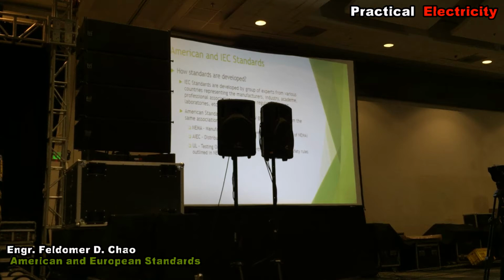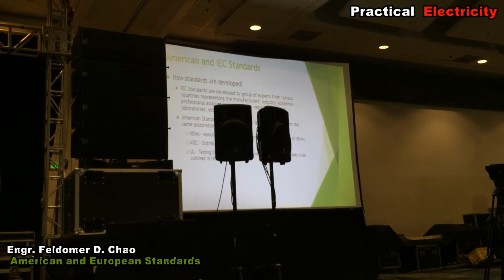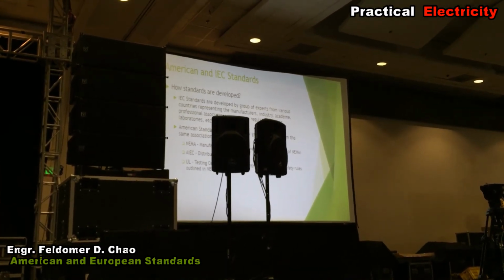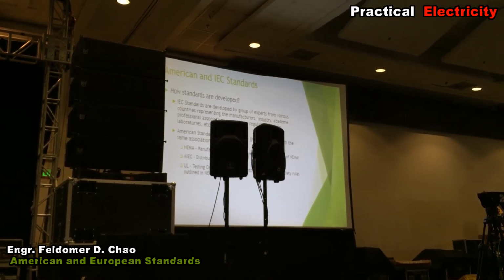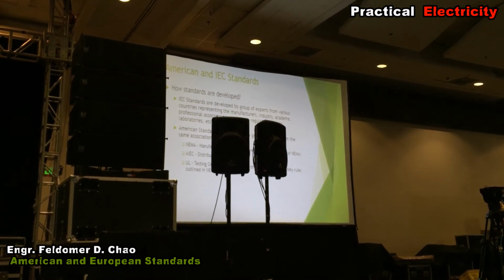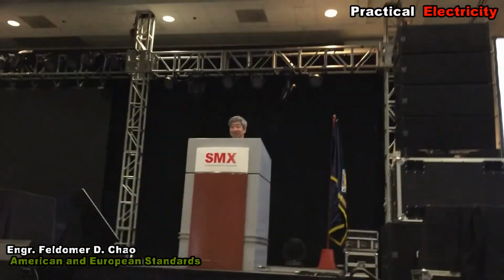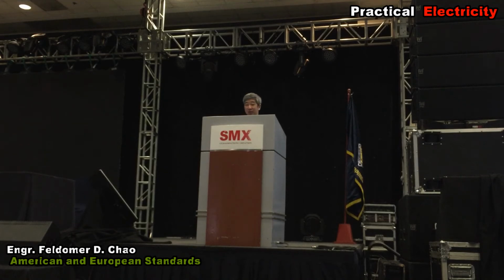Like for medium voltage, we have one coming from ICEA and one coming from AEIC. It's only recently that they harmonized their particular standards. For manufacturers, it's going to be the lower band, meaning I can comply based on this particular level of standards only. On the utility side, I want something that is much higher. So there's something that is not meeting the two particular standards.